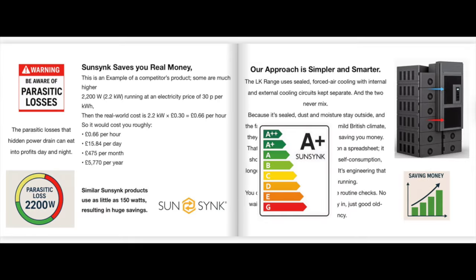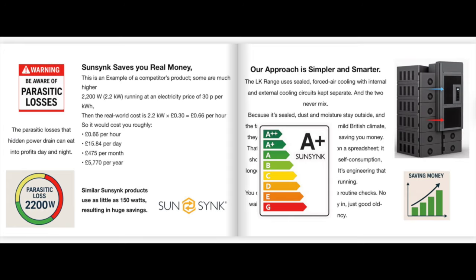This is something people don't actually realize, and this is really, really important. Because a lot of the time, if you're using a power hub or inverter because you have to, that's different. But if you're using a power hub or inverter to make money, then you must look at the parasitic loss. We call it maybe quiescent power, whatever - there's lots of words for it. This is the idling power, the energy the unit uses when there's nothing connected to it, when it's idle. It's chugging away, not generating power, not outputting, but it will still use energy.